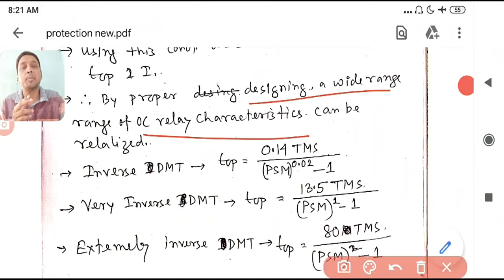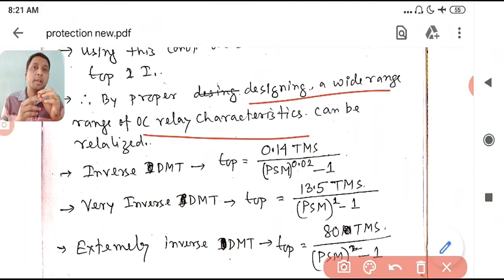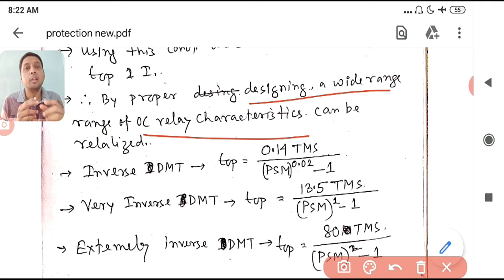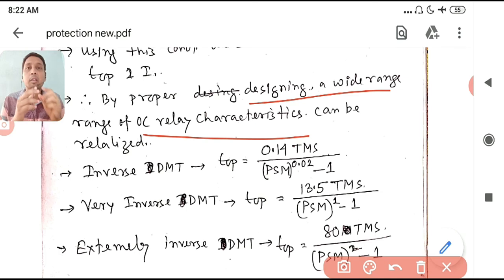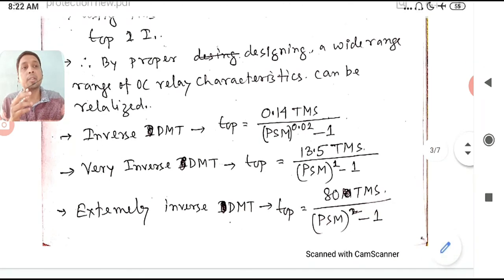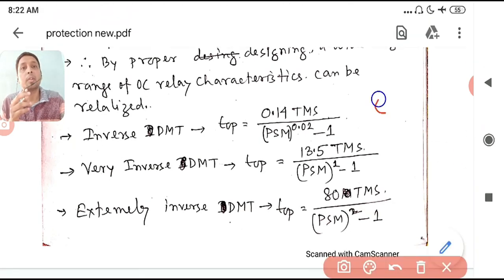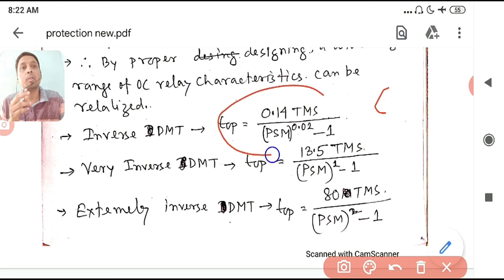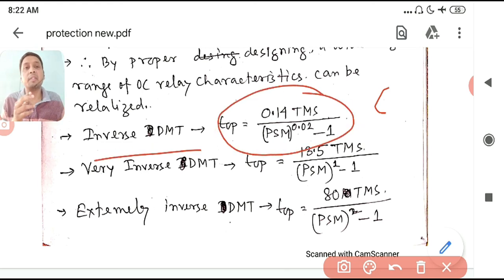By proper designing — varying the spring constant, damping constant, core saturation, and other parameters k, S, D — you can obtain three different IDMT characteristics: Normal Inverse (standard IDMT), Very Inverse, and Extremely Inverse.